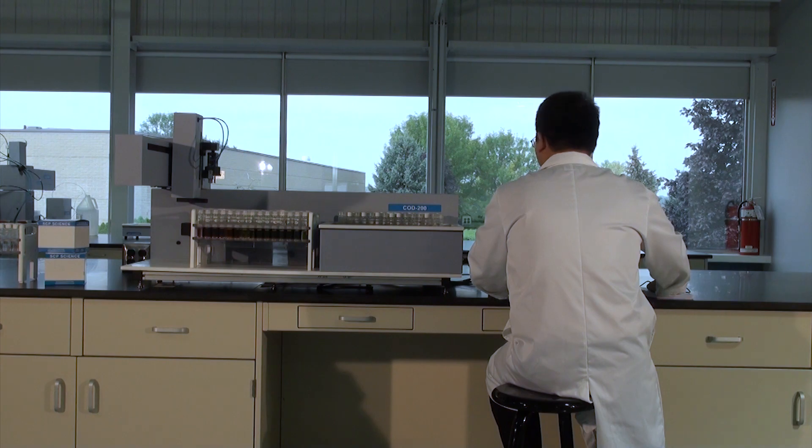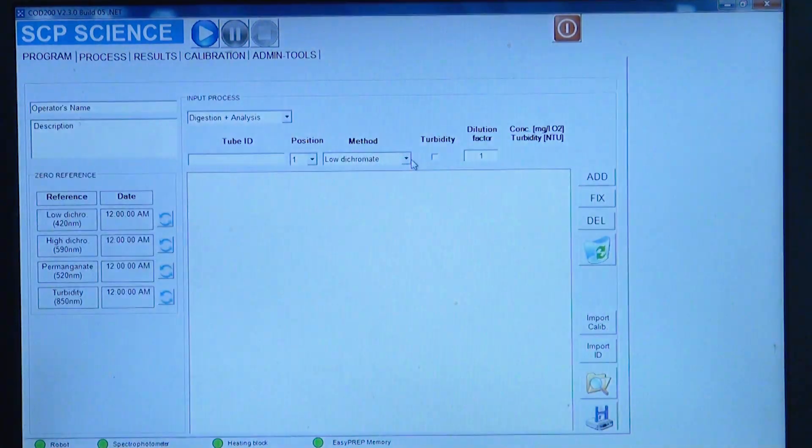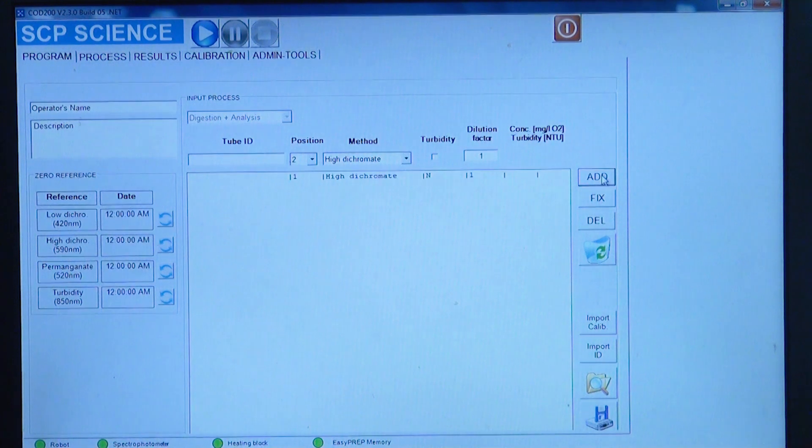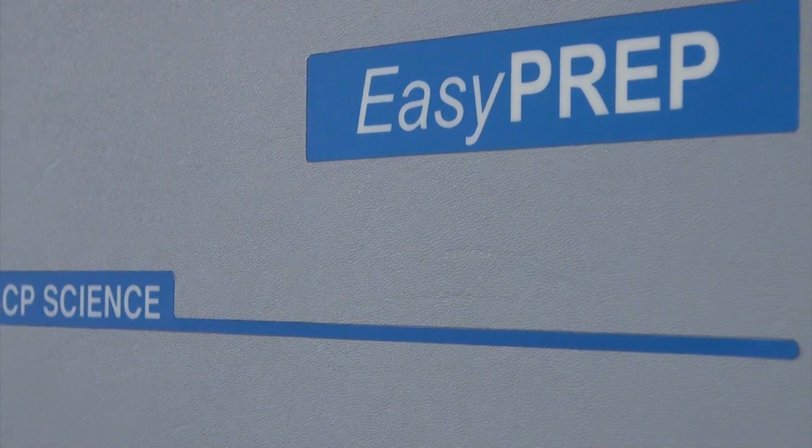Samples are individually timed based upon user-defined values for accurate COD analysis. Results are exported in a CSV format to automatically import to your LIMS.